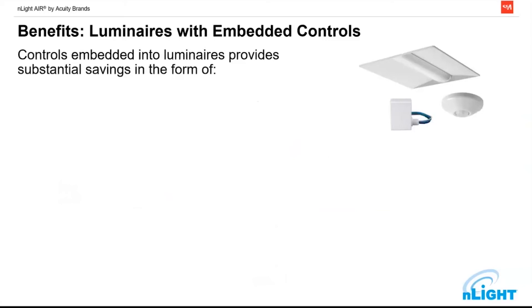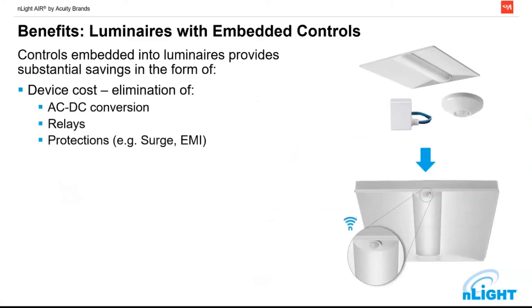With our embedded controls, we're taking essentially three pieces — a light fixture, an occupancy sensor, and a power pack — and converting into one. The advantage Acuity has as a lighting and lighting controls manufacturer is that out of the box this fixture has a sensor and nLight module and a photo cell, and it is all ready to go. So you've cut down on your cost for components and installation costs as well. For a retrofit or new construction application, all you need is power going to the light fixture, 120 through 277 volts. We don't need to run dimming wires or worry about surge suppression or AC-to-DC conversion like you'd normally see going from a power pack to an occupancy sensor.